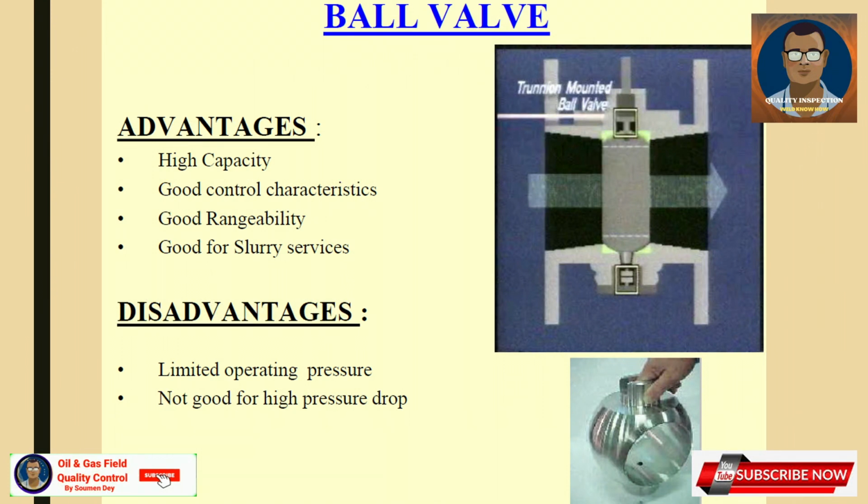Ball valve. Advantages: high capacity, good control characteristics, good rangeability, good for slurry services. Disadvantages: limited operating pressure, not good for high pressure drop.